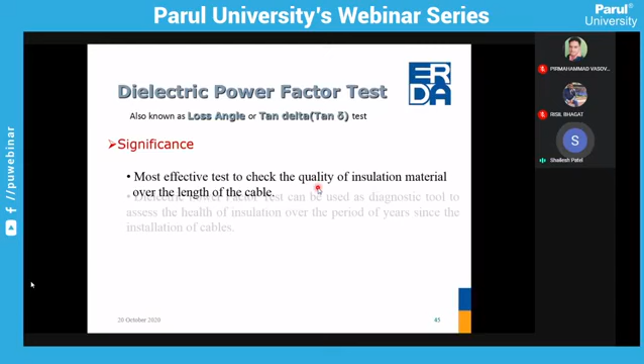This dielectric power factor test will give the current flowing through the conductors. Here is the main heart of this tan delta measurement. Just you understand this one, then it will be easy for you to understand the dielectric power factor test or the tan delta test. As we know that for any ideal capacitor, when the angle between voltage and current is 90 degrees, it is called an ideal capacitor. But normally it never happens in the field conditions. There will be some responsible parameters. Even insulating material itself will allow some current to flow through the insulating material. So it will give some resistive components.